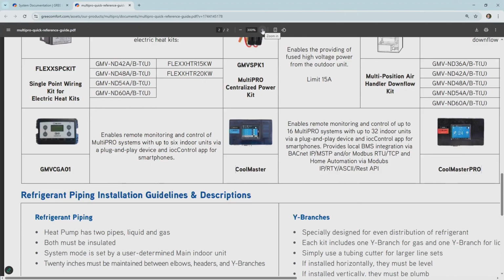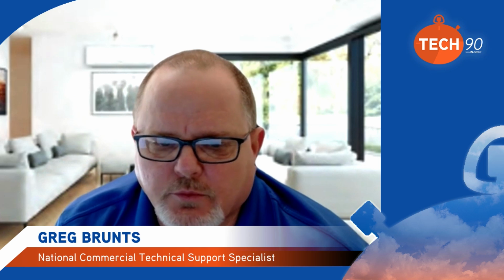I actually like the Cool Master myself better than I do the central control. But if you said you got 7 indoor units, keep in mind that GMV CG-A01 only does 6 indoor units. So you'd have to use 2 of those. Well, on one outdoor unit, we can't use 2 of them. So you would have to either use central control or Cool Master.